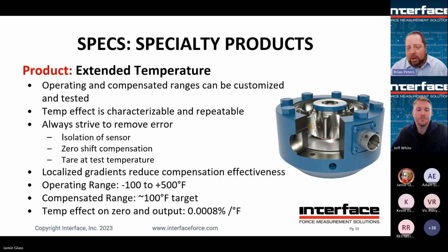It's usually behind the label on an interface load cell. You'll feel a little hard cover there. If you have a localized temperature delta at that spot versus the rest of the sensor, temp comp may be delayed or it may not even be accurate. So that's just something to keep in mind. You want to try to keep things as consistent as possible. And then you've got to factor in, is there time for everything to get to temperature? Temperature compensation might lag a little bit if there's an extreme change in temperature. It happens very quickly, and the whole load cell hasn't been able to get up to temperature. So those are things to keep in mind.